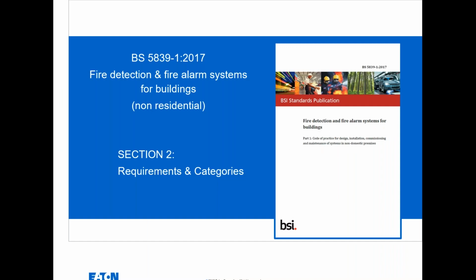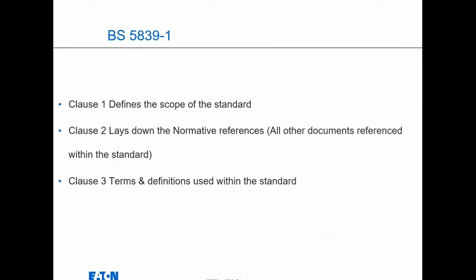So 5839 does cover non-residential, so it's commercial properties, which is mostly what we put fire alarm systems in. Most dwellings, unless they're now high residential flats and big buildings, generally only have smoke alarms for mains powered or domestic smokes, and we as Eaton do not make those. So within the document, clause 1 defines the scopes, clause 2 lays down the normative references, and clause 3 picks up T's and C's, terms and definitions, not conditions, used within the standard. So if there's any acronyms or anything like that, you can pick it up in clause 3.